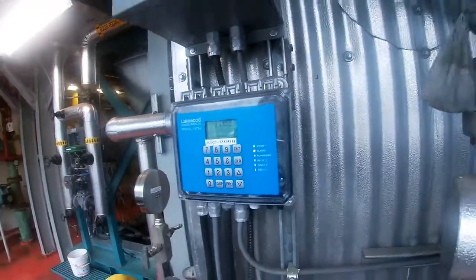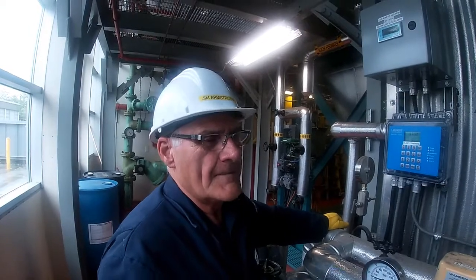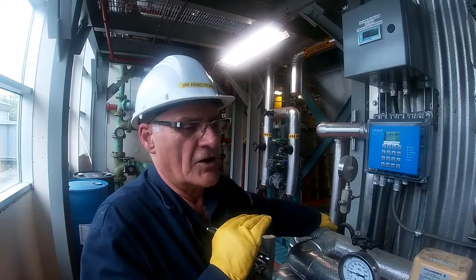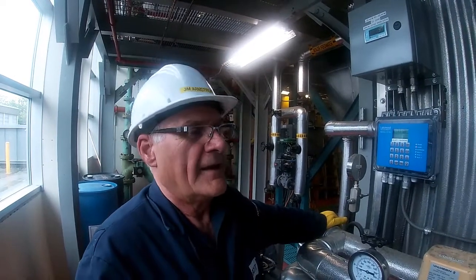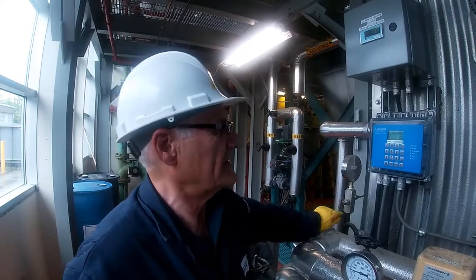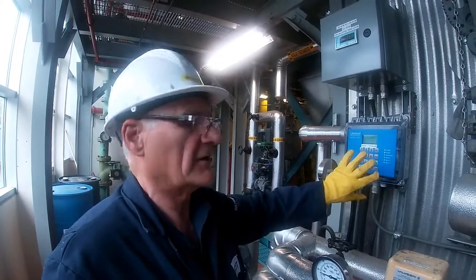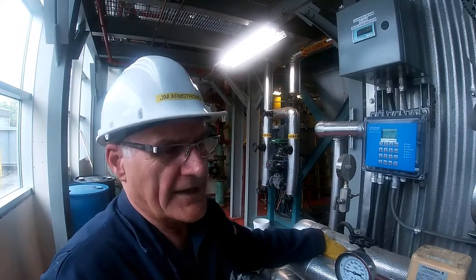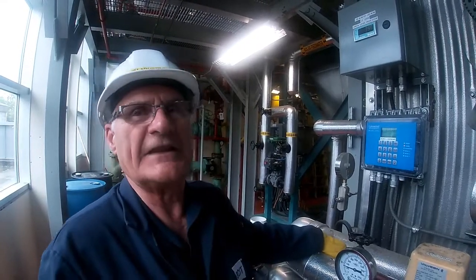Every plant is different. You do operator tests on the boiler water and determine when that water is really good. It's got the right amount of caustic in it, the right amount of sulfite in it, the right amount of phosphate in it, the right amount of amine in it. And once you've got all of those right, we look to see what the conductivity is. This can be calibrated fairly simply. It's just a 1-point calibration, and it's accurate when the boiler is hot because there's no temperature compensation or any of that kind of stuff in it.